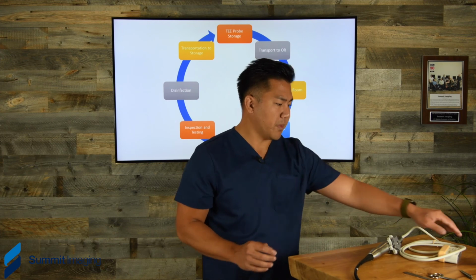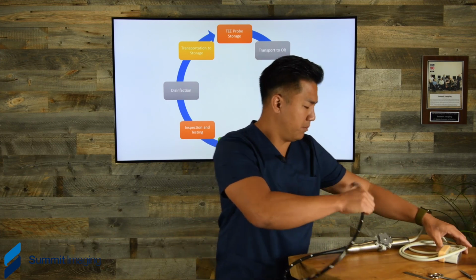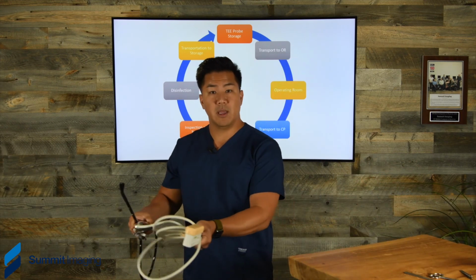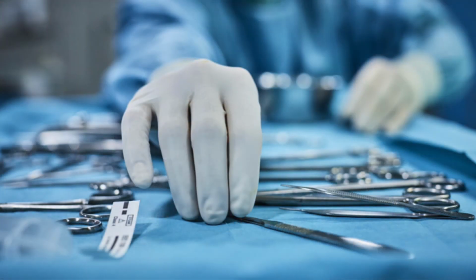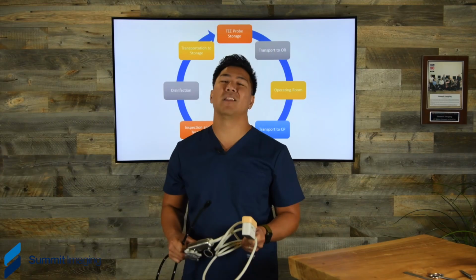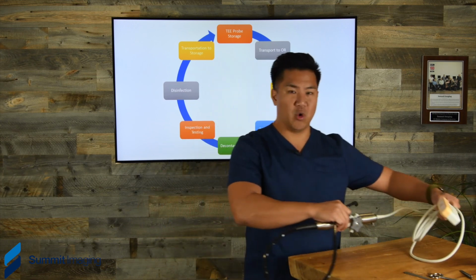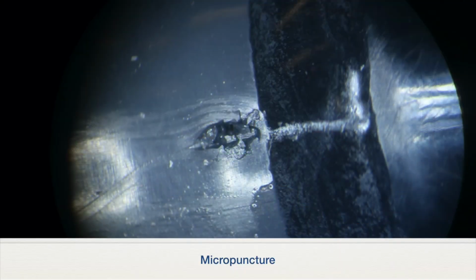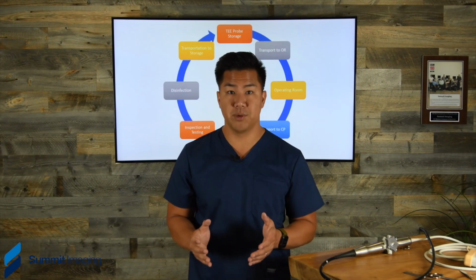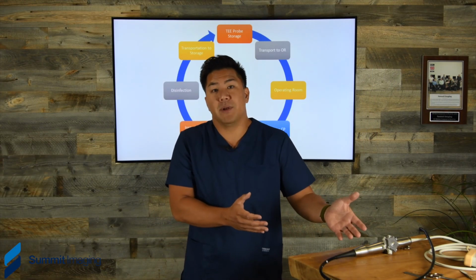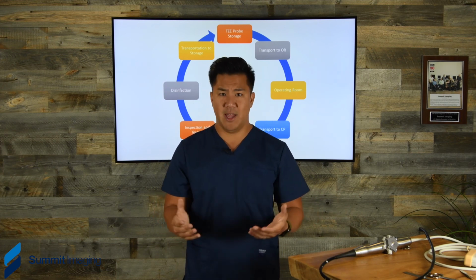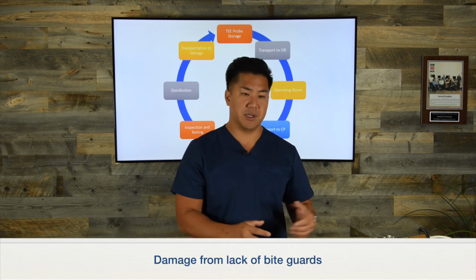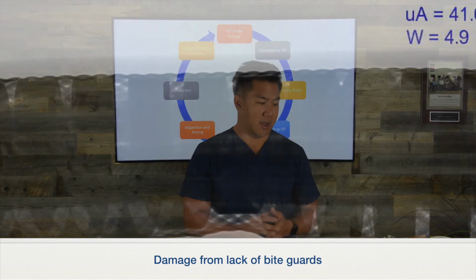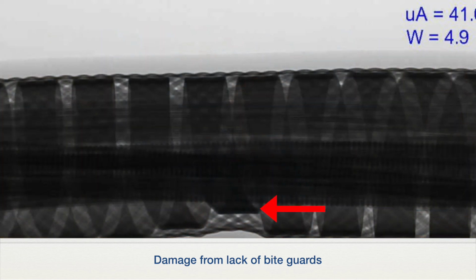And so having the T-probe completely stored away from the surgical tools in the room will prevent a lot of damage. We see a lot of micropunctures in these bending rubbers. It's probably the most common failure for T-probes, and this is a common issue. Also, a lack of use of bite guards can cause some severe damage here as well.